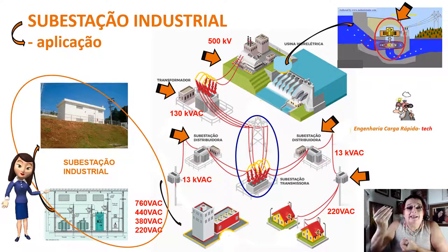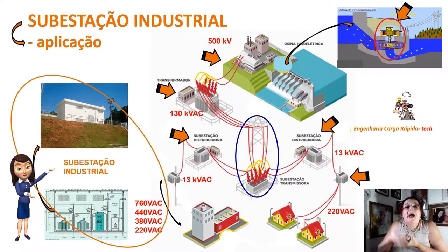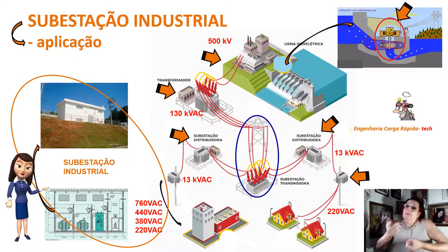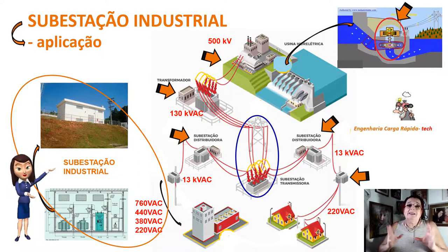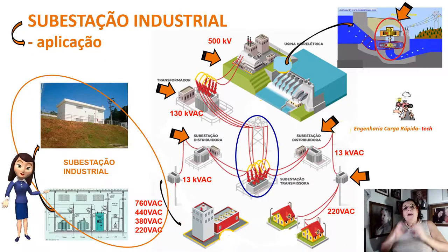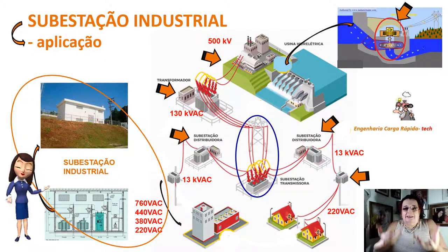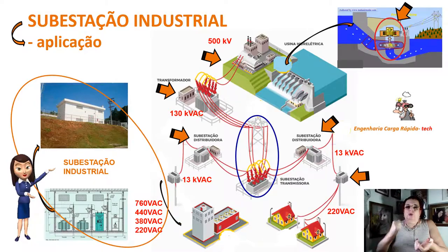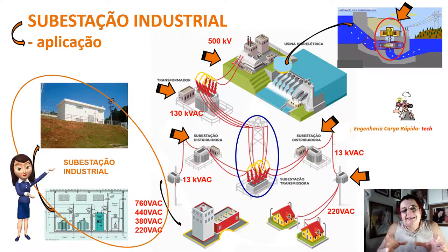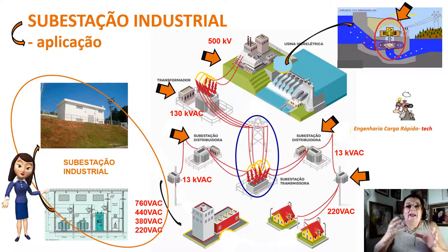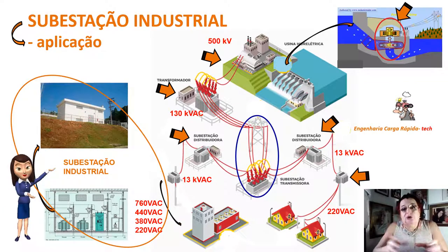Quanto maior a tensão, menor o diâmetro e a seção do cabo. Por isso é interessante termos máquinas industriais com 380 ou 440 volts. Quem alimenta essas máquinas é a subestação industrial da própria indústria, sendo a responsabilidade de manutenção e aquisição de equipamentos da própria indústria.